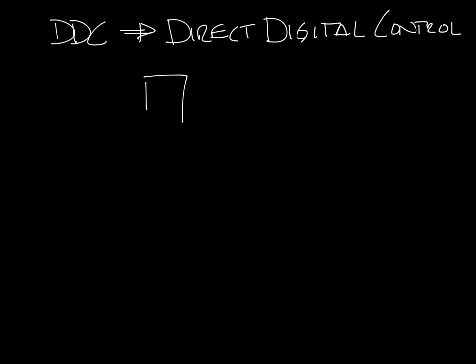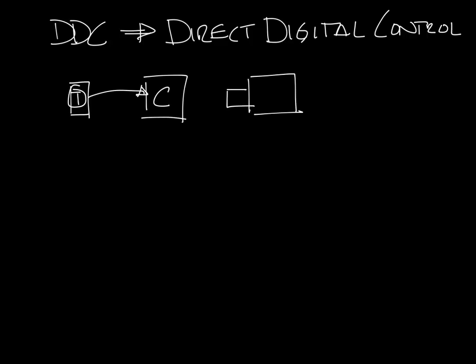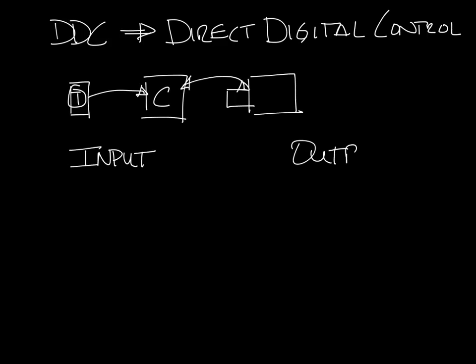As a refresher, the controller is the brains of the VAV box. It takes the set point and space temperature from the thermostat and the airflow information from the VAV box, and decides what the box needs to do — open or close the damper, turn on heat, and so on — to maintain comfort in the space. So how does it take this information and adjust the box for comfort? This is where inputs and outputs come in.